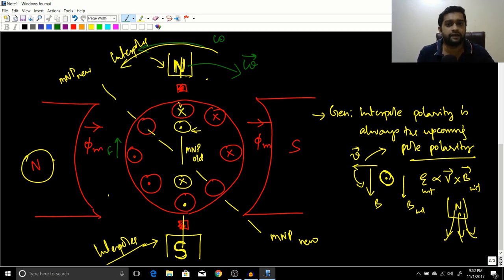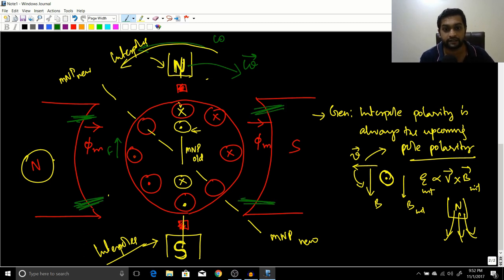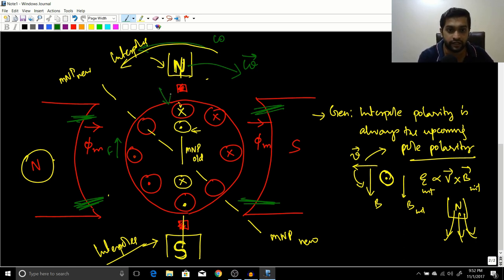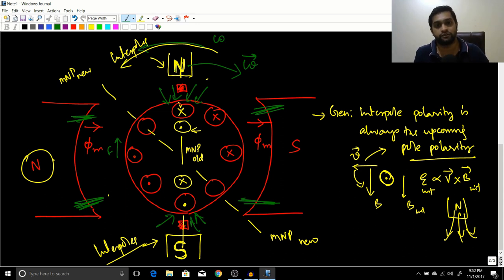This is not a complete solution. Interpoles can only cancel sparking at the brushes — the flux weakening effect due to armature reaction still exists. Flux weakening and flux addition happen at the pole tips, and the interpole has no effect on the pole tips — nor should it, as the interpole should only concentrate on the commutating conductors. For a complete solution that also reduces flux weakening, the third solution — the compensating winding — is needed, and that will be the next topic.